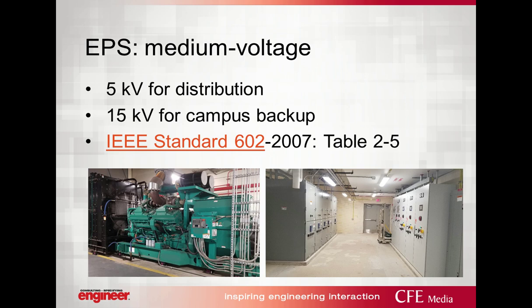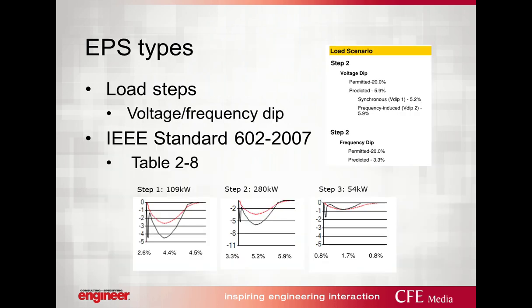Now, if I want to do full campus backup, then I might be going 15 kV, in which case I'm either going to parallel or just simply replace the utility company entirely. That's the generator on the left. Now, if you're going to determine how big to make your campus backup gen set, I'm listing in there IEEE standard 602-2007, because there's a table in there that actually lists the service entrance demand for 37 different hospitals throughout the country based on the square footage, number of beds, etc. So it's a really useful reference for designers wondering, how big should I make these gen sets if I'm going to be doing medium voltage applications?